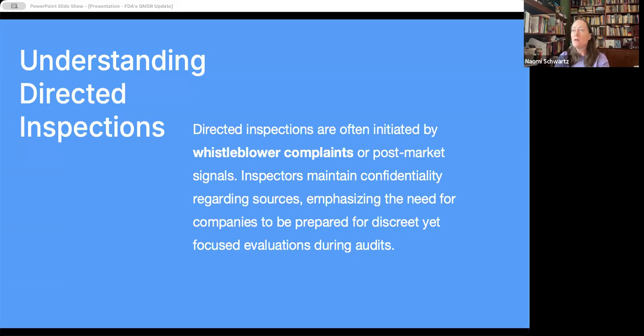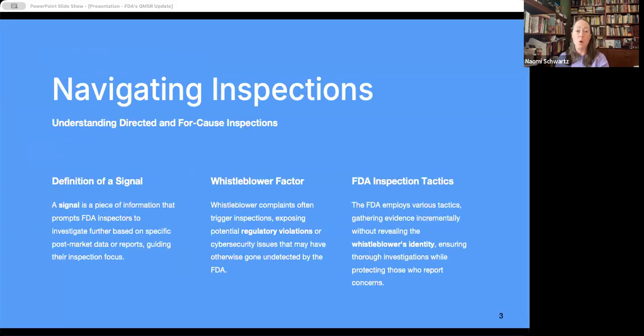And you need to be aware when staff members raise concerns and don't see action taken, and this goes back to questions about management review. If you're not following through and somebody decides that it is important from a safety perspective that these issues be uncovered and they whistleblow on you, you will have an inspection, and it will be associated with cybersecurity, and they will dig very deeply into whatever is going on, because they need to understand if there's a situation that poses harm to patients, what is going on, and what element of your quality management system is breaking down.